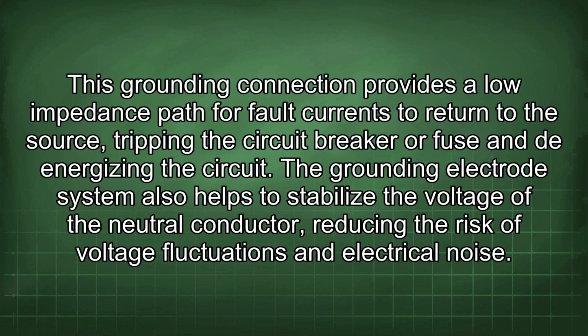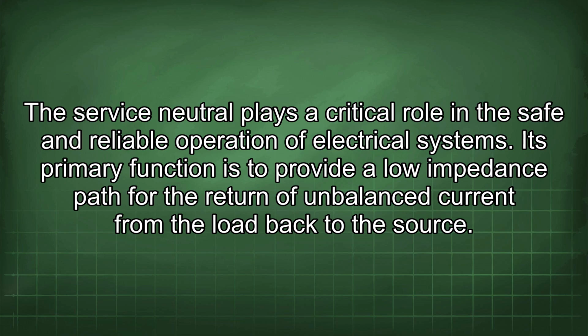This grounding connection provides a low impedance path for fault currents to return to the source, tripping the circuit breaker or fuse and de-energizing the circuit. The grounding electrode system also helps to stabilize the voltage of the neutral conductor, reducing the risk of voltage fluctuations and electrical noise. The service neutral plays a critical role in the safe and reliable operation of electrical systems.